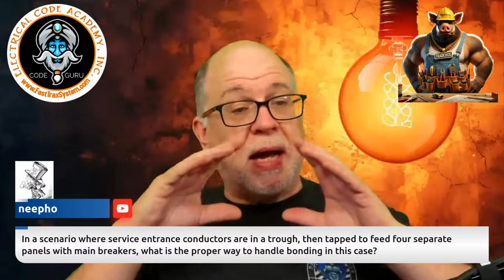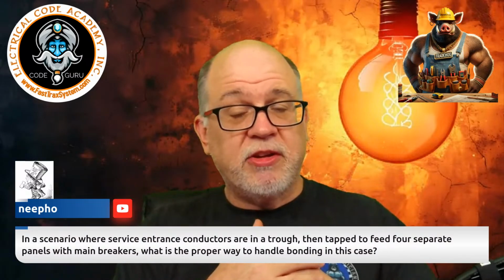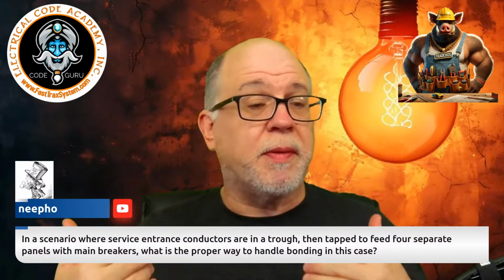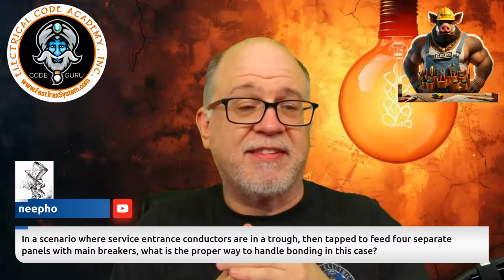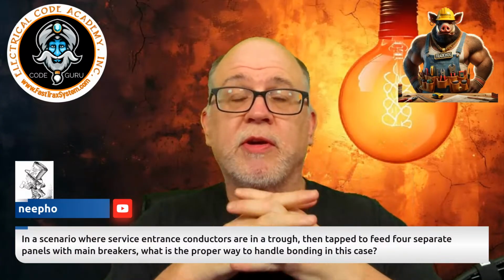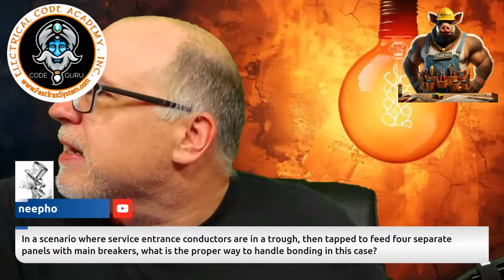So if you're talking about bonding, the easiest thing to do is to use the grounded conductor to bond all metal parts on the supply side, if that's what you're talking about. So you get the allowance to do that -- oh, hold on, I'm about to get dropped off of TikTok.